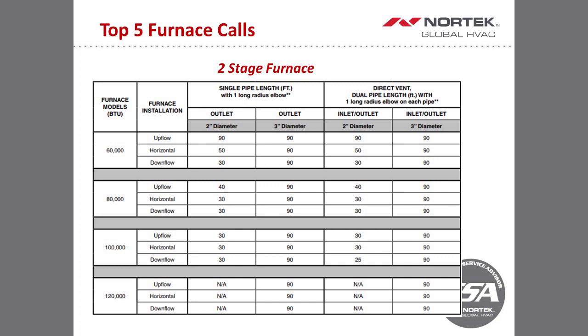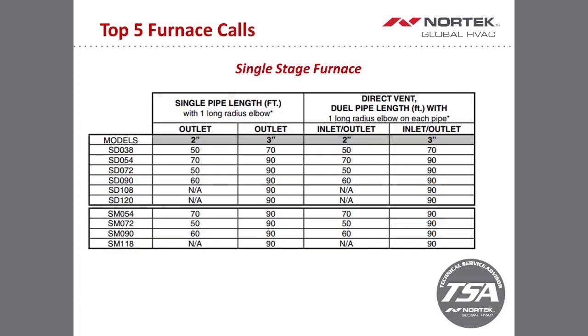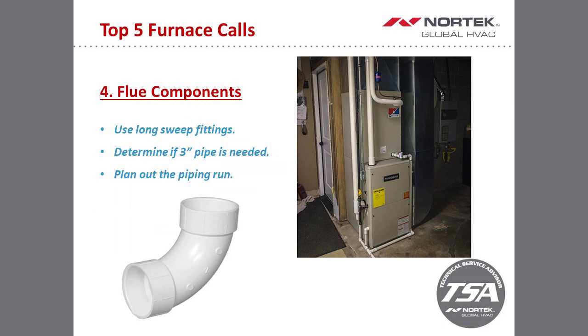Also, believe it or not, we do get the question of what does NA mean? It's non-applicable, meaning that you cannot use 2-inch pipe on a 120,000 BTU furnace. That's what you would see on this table here for a 2-stage piece of equipment, and also on the single stage on the 108 series BTU furnace, you cannot use 2-inch. It's got to be 3-inch. And this again goes with when do we go to 3-inch pipe? We always advise to use long sweep fittings. Don't use plumber 90s or what I would call a regular 90. You always want to use long sweep because that will cut down on the restriction. And if you end up using regular 90s or plumber's 90s, I would add a few more feet onto that, 5 feet per 90. So plan out your piping run.